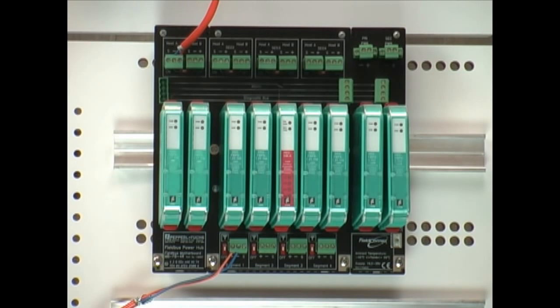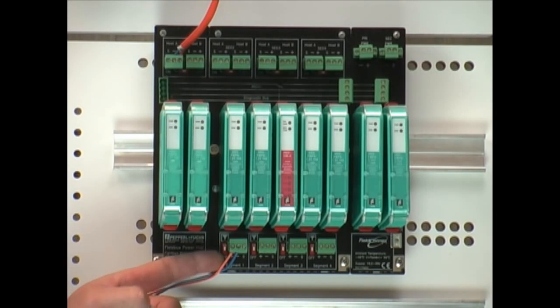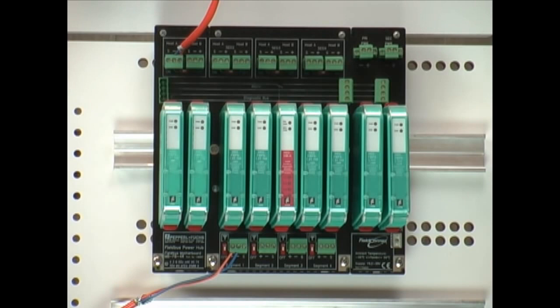Now the various power supplies available from different manufacturers offer redundancy of the power supplies as well as usually a built-in selectable terminator. Each Foundation Fieldbus segment needs two terminators, one at each end of the segment, and so having it built into your power supplies is a convenient way to make sure that's included.